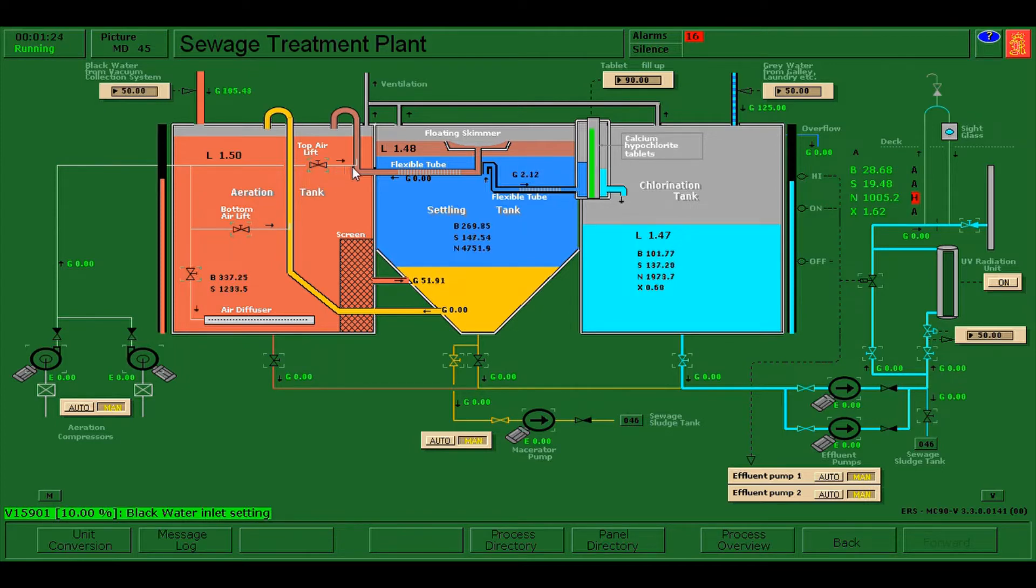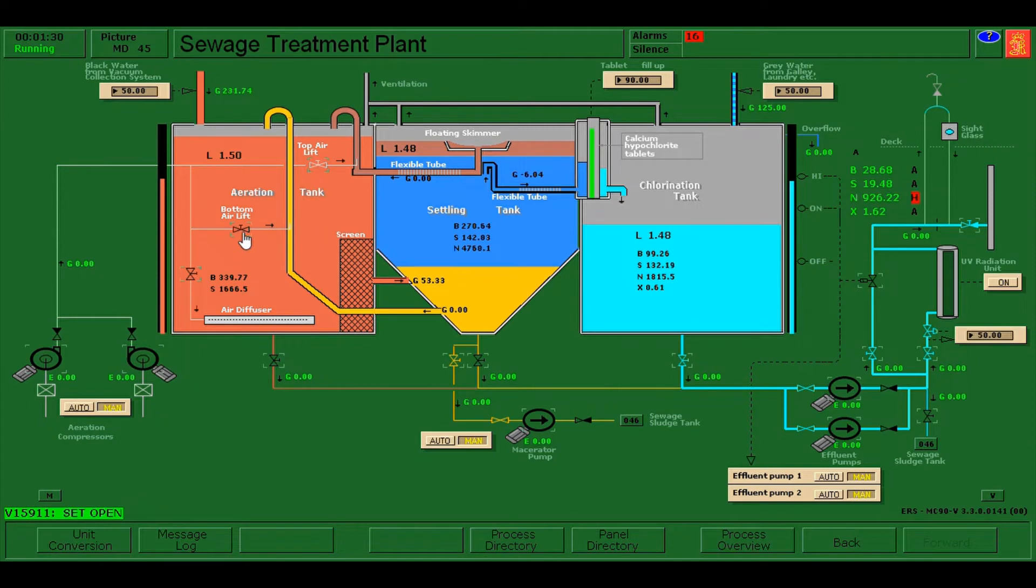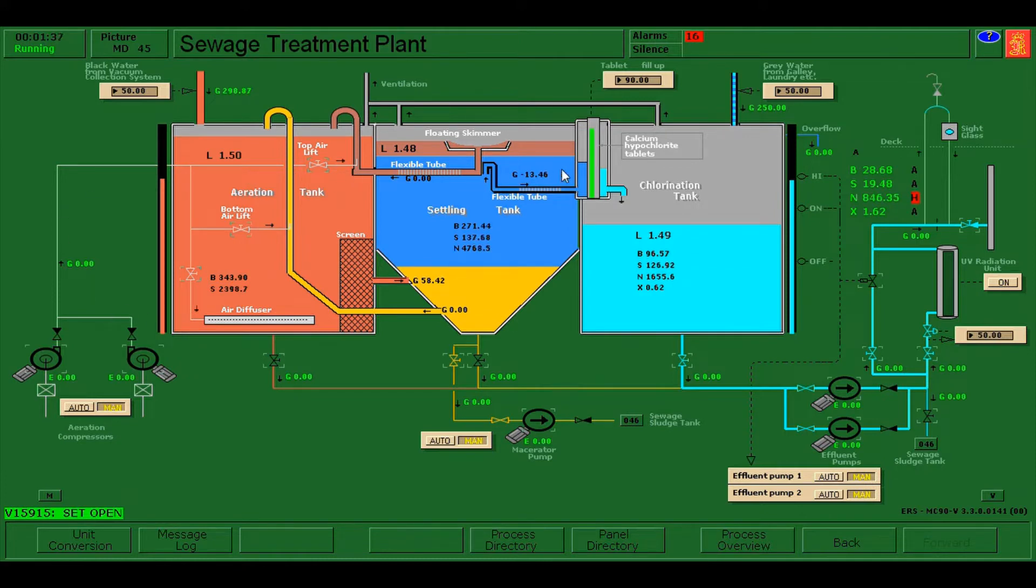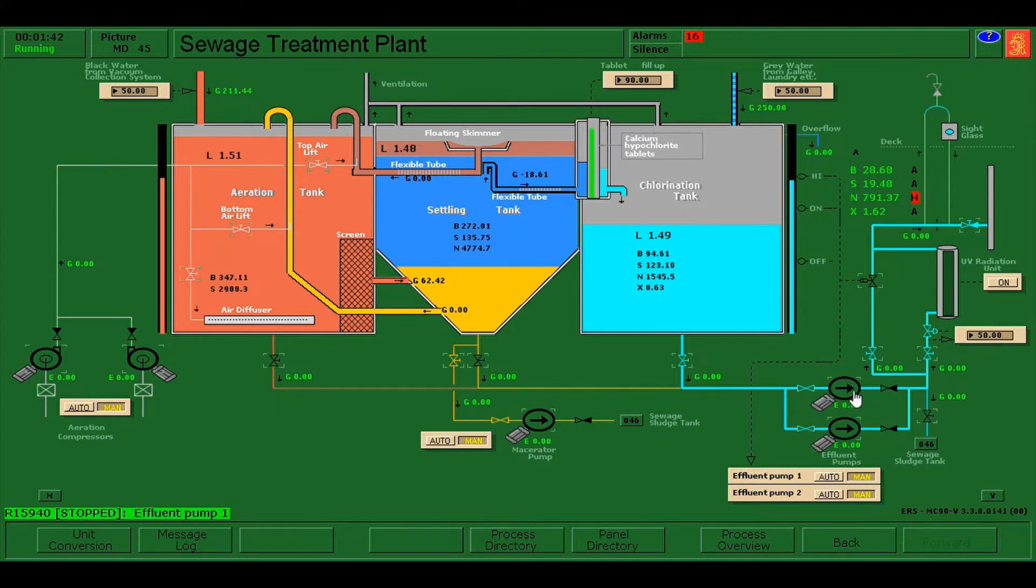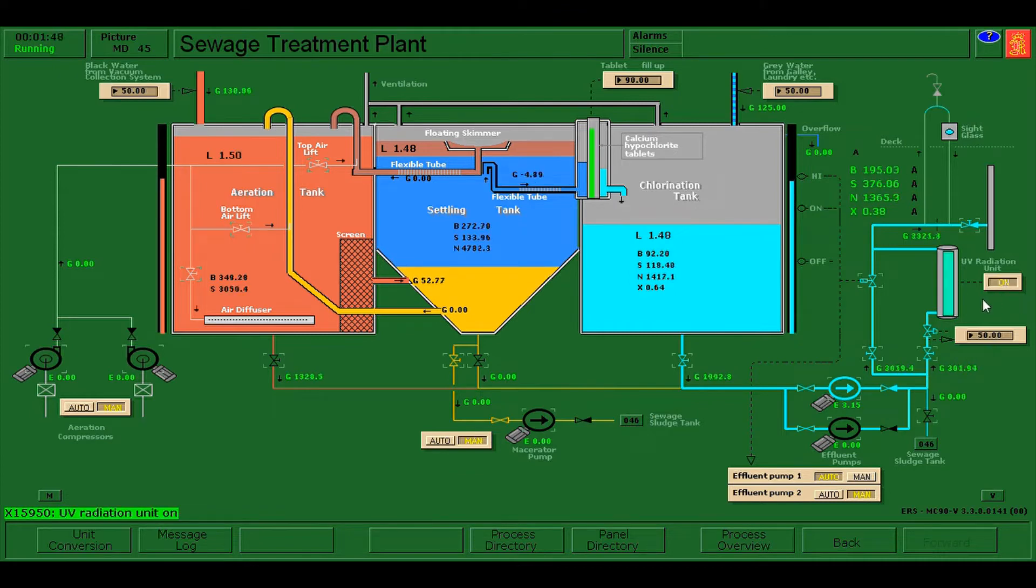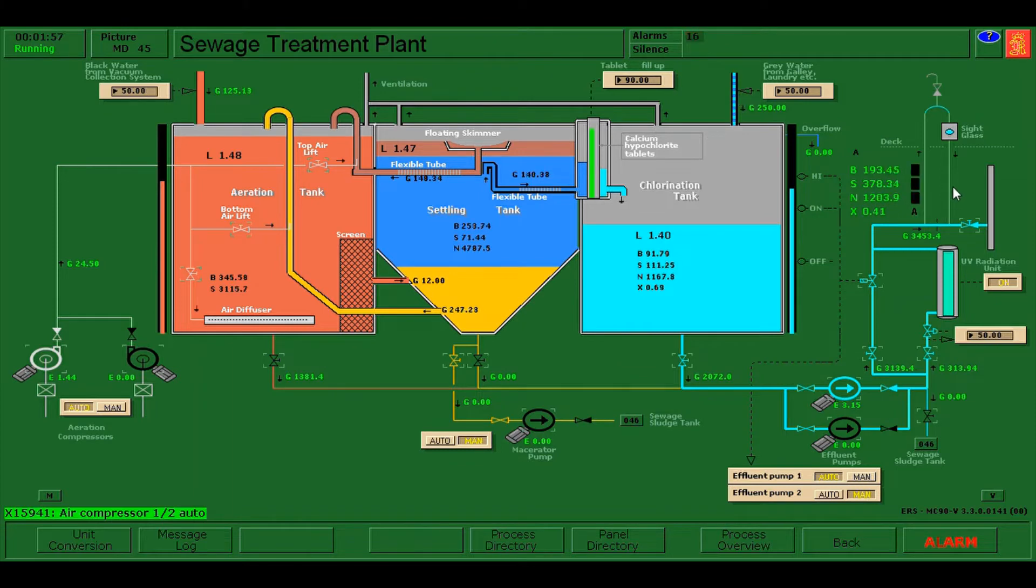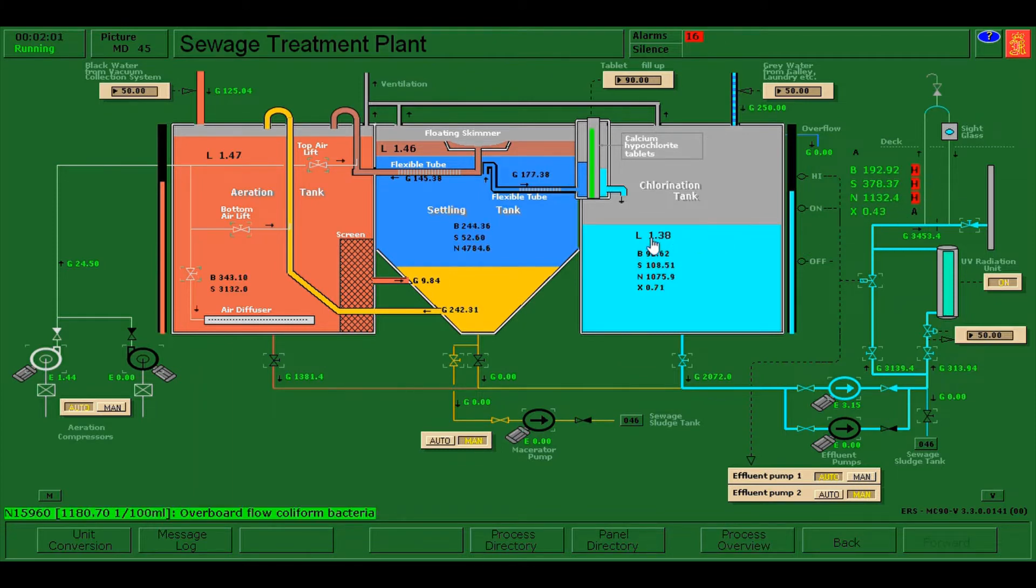The remaining here is we need to open also the discharge outlets for the air going to our STP. I think the lines are already lined up, we can now start our effluent pump number one and put it on automatic. Put the UV radiation unit on and I will start also the blower. There is an alarm, press Shift 12 to silence and acknowledge all the alarms.